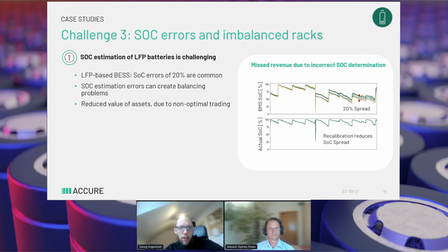Third challenge: SOC errors and imbalanced racks. Especially for LFP battery systems, SOC errors are common - we've seen errors of 20% or above. These SOC errors can create balancing problems and imbalances, and additionally reduce the value of the asset, because if you cannot use its entire capacity due to BMS or SOC estimation errors, you cannot optimally trade it.